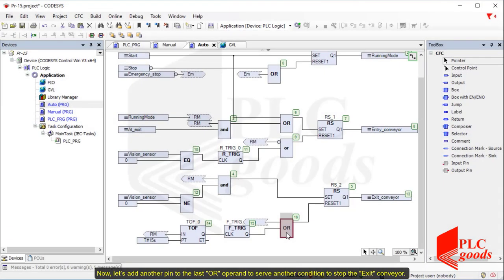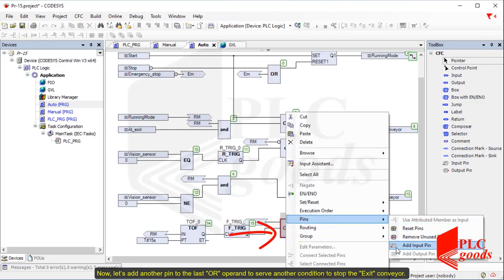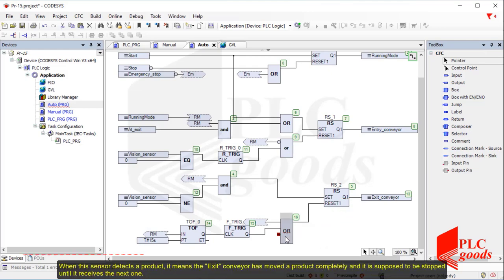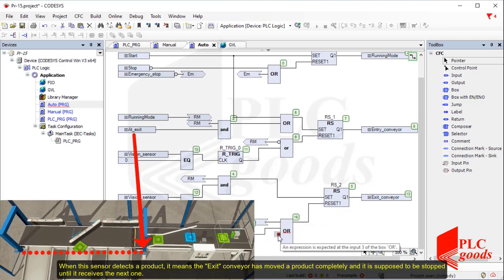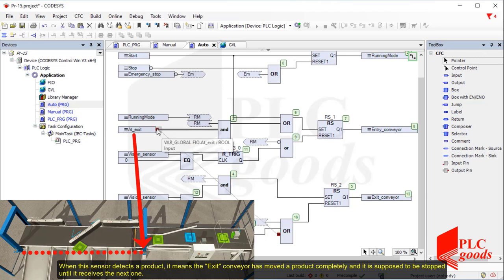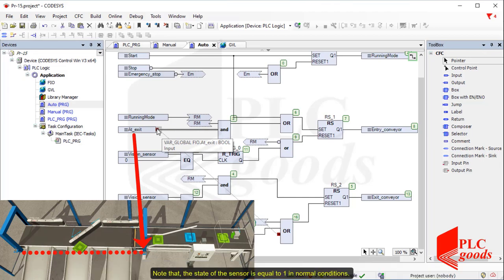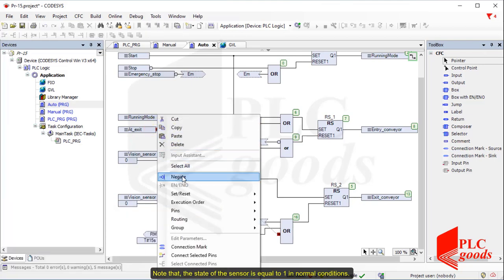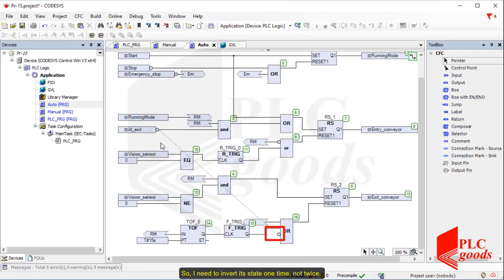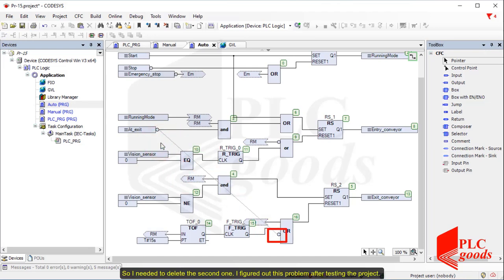Now let's add another pin to the last OR operand to serve another condition: to stop the exit conveyor when this sensor detects a product. It means the exit conveyor has moved the product completely and it is supposed to be stopped until it receives the next one. Note that the state of the sensor is equal to one in normal conditions, so I need to invert its state one time, not twice. I figured out this problem after testing the project.